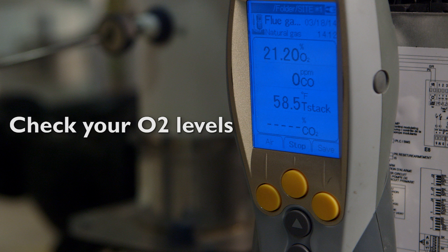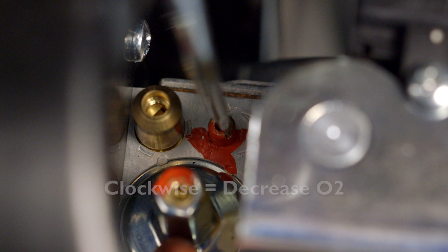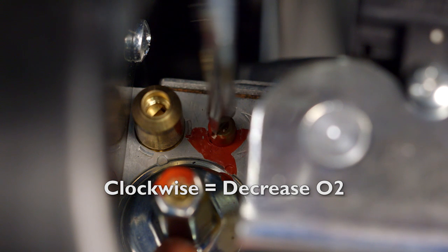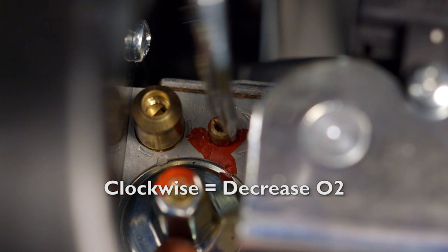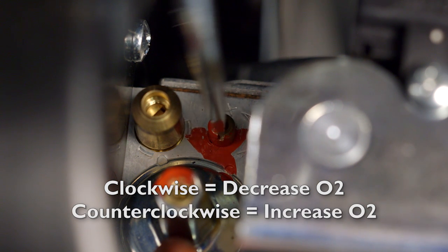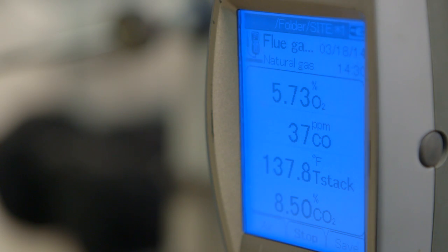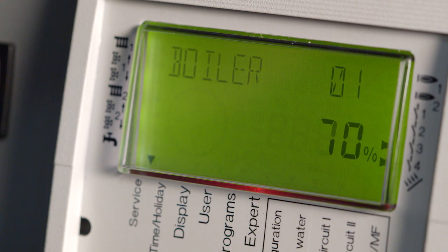Check that your O2 levels are within the value indicated in the manual that accompanied your unit. You can find this information by referring to the table found in your manual. If you need to, you can correct the value on the boiler by turning the adjustment screw clockwise to decrease O2, or counterclockwise to increase O2. After making an adjustment, allow the values to settle again and check against target O2. Once you have calibrated a maximum fire rate, you must then calibrate that module at minimum fire rate.